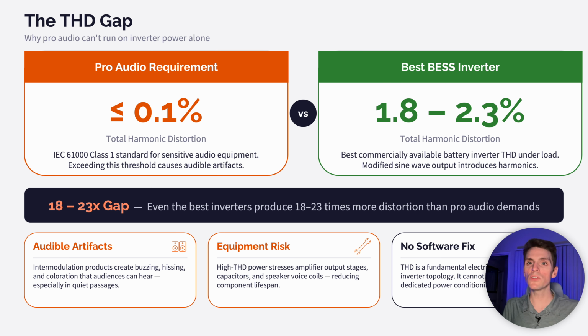The core problem is the total harmonic distortion. Professional audio needs THD below 0.1%. The best grid-forming inverters on the market, even 2 megawatt units designed for hospitals, deliver 1.8 to 2.3% THD under nonlinear loads. That's an 18 to 23x gap. This causes audible artifacts like buzzing and coloration that most anyone would think something sounded wrong, which also stresses the amplifier components greatly. And it's a fundamental electrical property of the inverter topology itself, and you cannot fix that with any software.